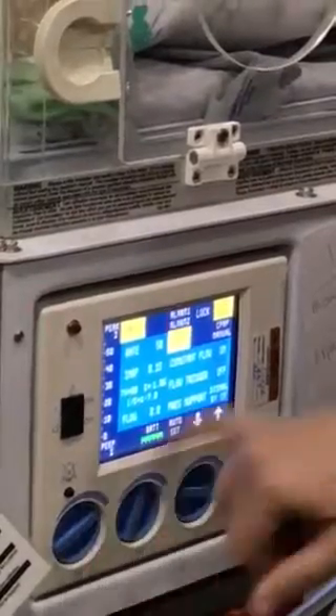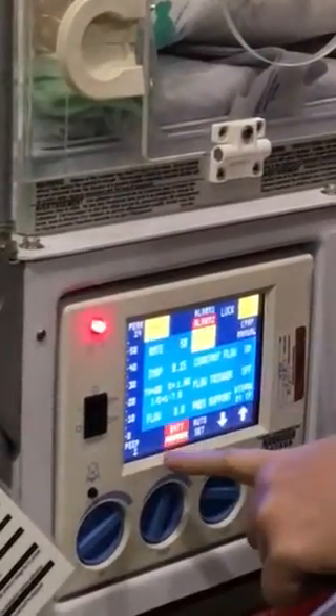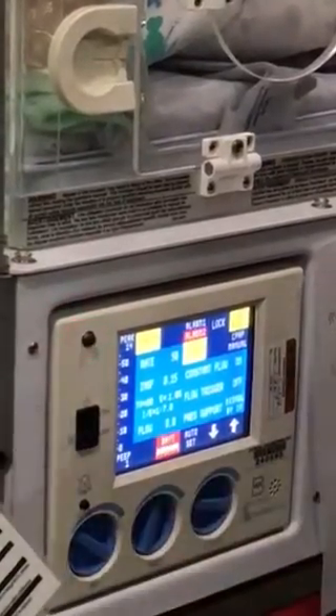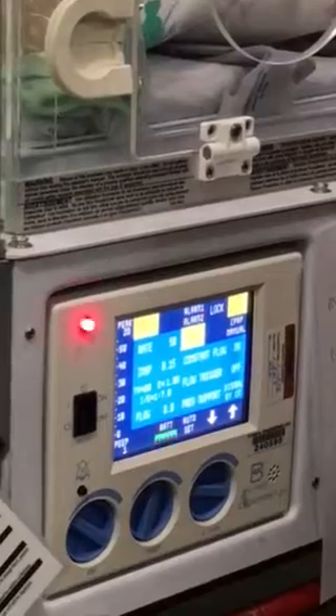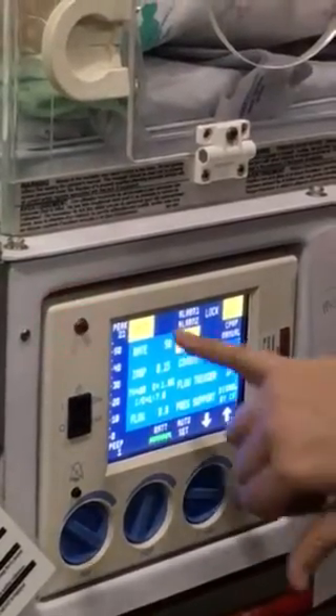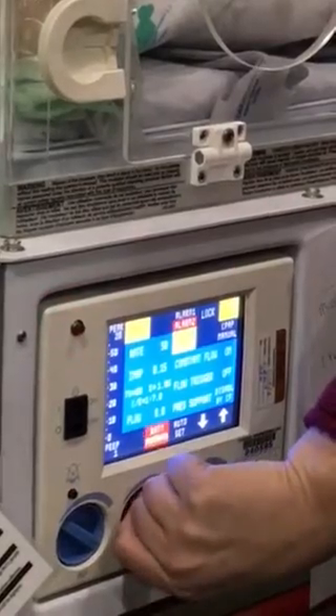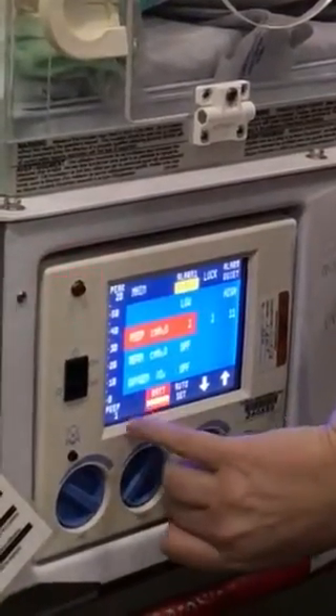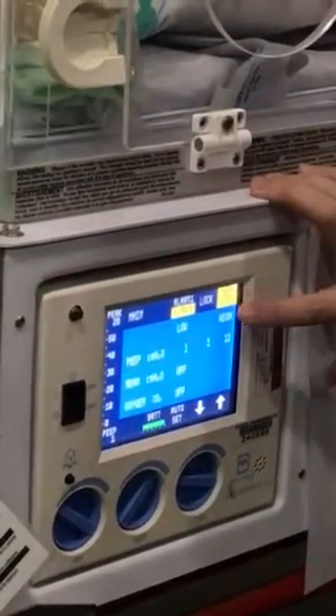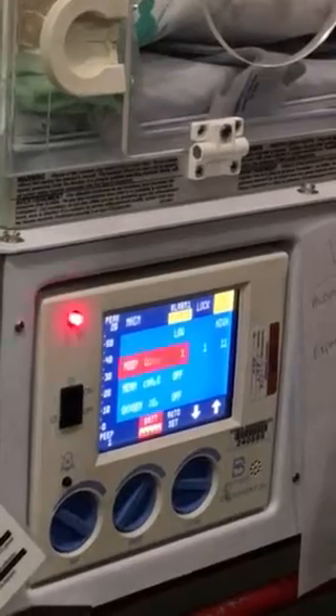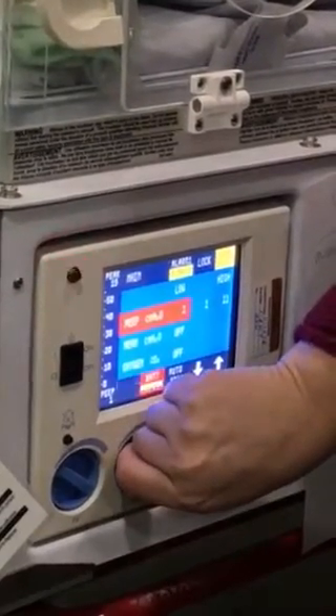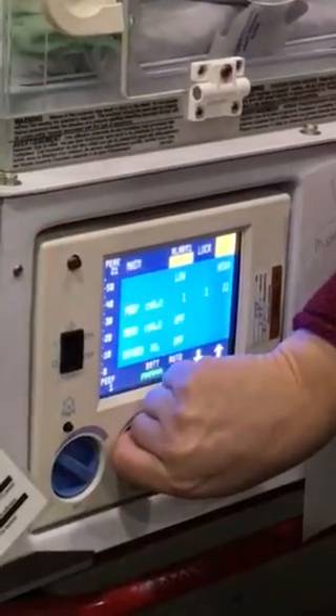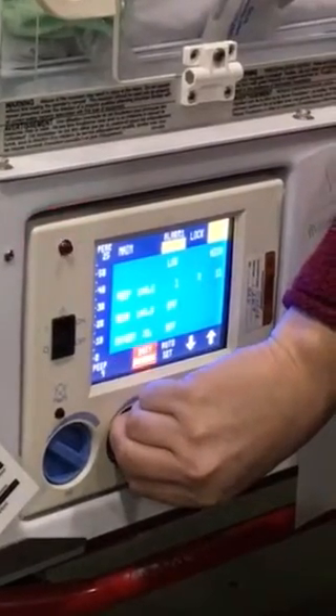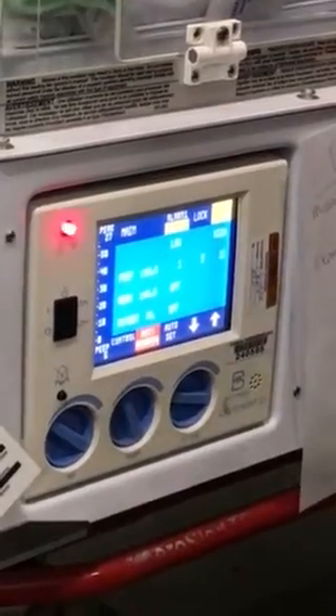Okay? So your PIP, your peak inspiratory pressure, is gonna read here. And your PEEP's gonna read here. Okay, so you see the 20, approximately 20, and then I'll go with the PEEP. PEEP is gonna read here. So if it alarms, just hit the silence here. If you hit it twice, you'll get 2 minutes. Okay, 20/5. Then the rest of the stuff is touch screen for you.